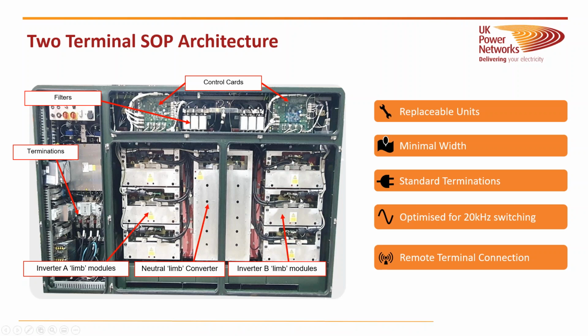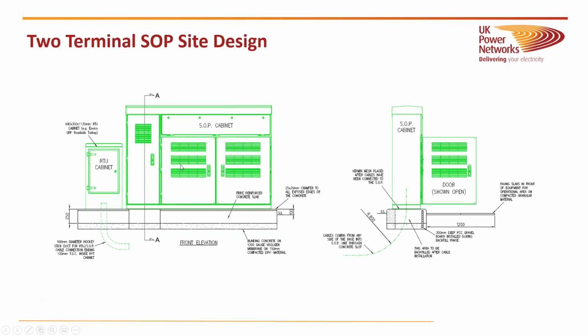It's also had to be designed to work with these new 20 kilohertz silicon carbide devices. As Luca said, they're very efficient, losses are a lot less, but to keep the noise to a minimum, we don't have any fans in the 2T SOP. Well, there is a fan, but it only operates at peak current, so for very limited amounts of time. So the thermal management is a really important part of this design. Particularly, inductors at 20 kilohertz have a lot of core losses, so they've had to be specially designed to limit those losses. And lastly, there's a connection to our remote terminal unit. There's a local RTU for this device that, if I go to the next slide, is here, and that connects to our SCADA system.